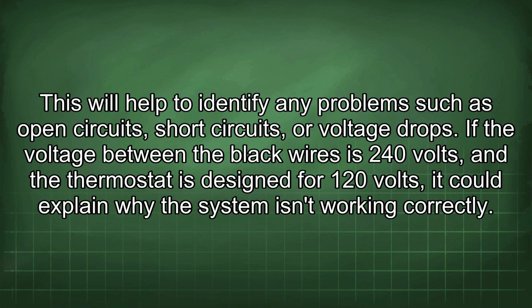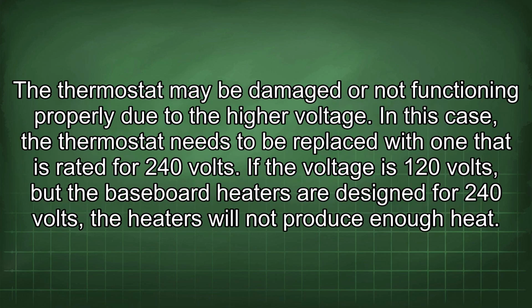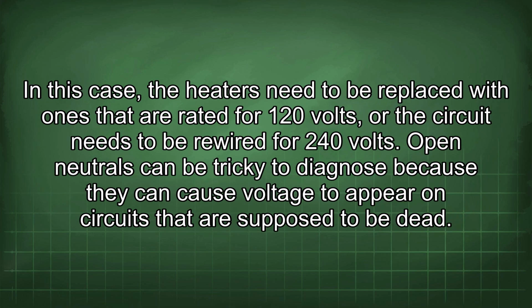If the voltage between the black wires is 240 volts and the thermostat is designed for 120 volts, it could explain why the system isn't working correctly. The thermostat may be damaged or not functioning properly due to the higher voltage. In this case, the thermostat needs to be replaced with one that is rated for 240 volts. If the voltage is 120 volts, but the baseboard heaters are designed for 240 volts, the heaters will not produce enough heat. In this case, the heaters need to be replaced with ones that are rated for 120 volts, or the circuit needs to be rewired for 240 volts.